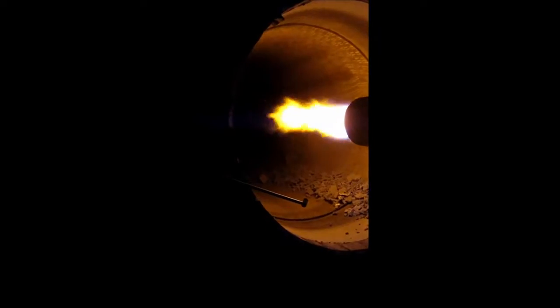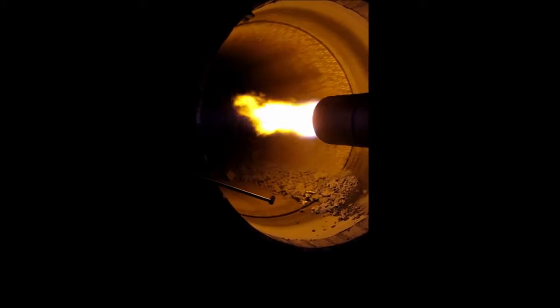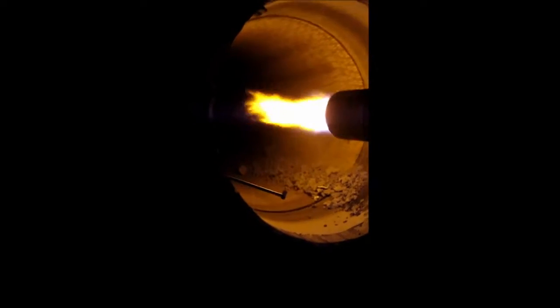On February 8, 2016, the JetFlex burner was ignited for the first time using natural gas as fuel. The plant operators noted that it was easy to start and gave them excellent flame control from the very beginning. Changes to burner settings were observed immediately in the flame. The operators also found they could transition smoothly from gas to pet coke and then to alternative fuels firing.